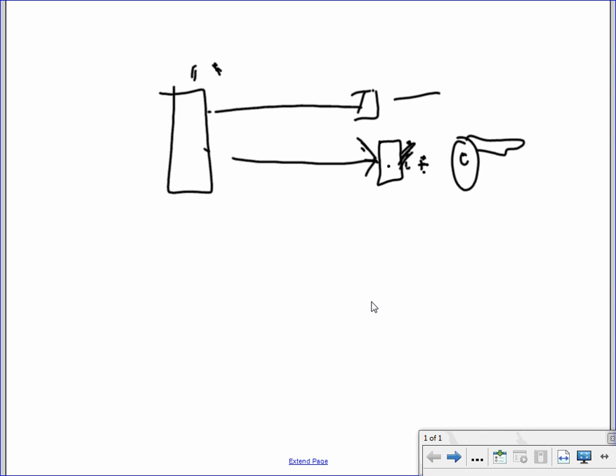So you provide them with a dry contact, normally closed. Well, we energize it. We give them a Form C relay. Form C contact, which is common, normally open on one side, normally closed on the other side. And they'll take it from there. They interface it with their control system however they want.